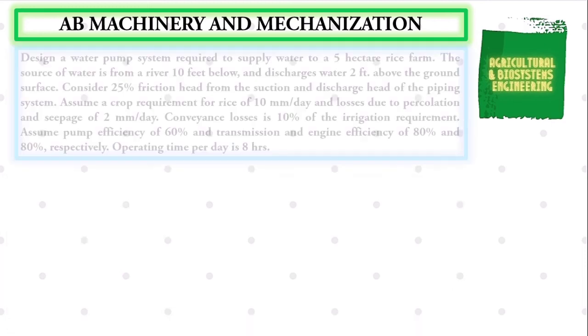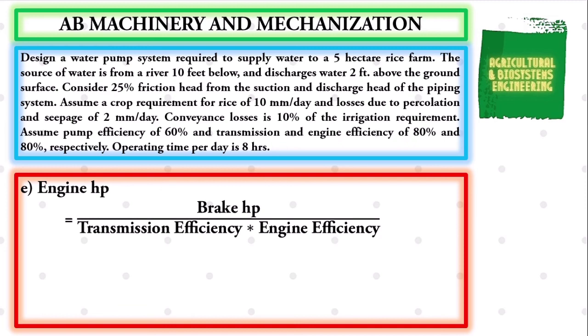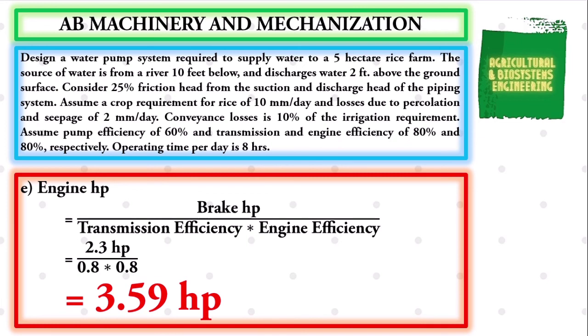The next value to solve is the engine horsepower or motor horsepower. The formula is: Engine HP = Brake HP ÷ (transmission efficiency × engine efficiency). Substituting: 2.3 ÷ (0.8 × 0.8), giving us a final value for engine HP of 3.59 horsepower.